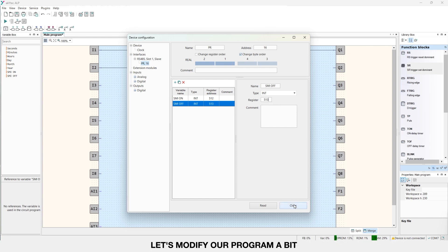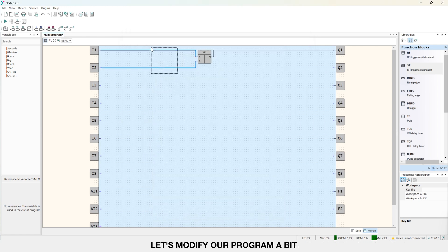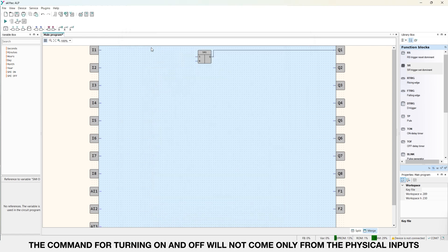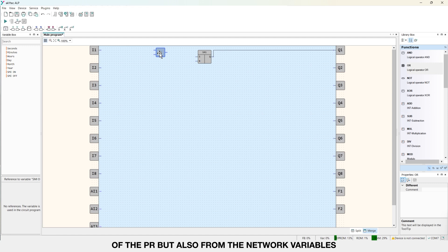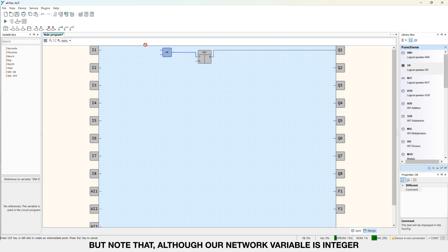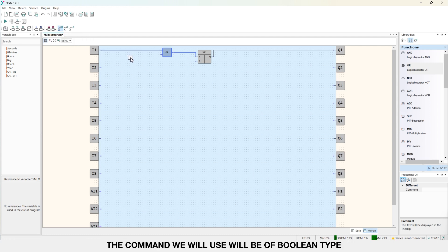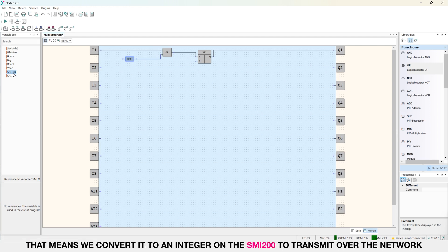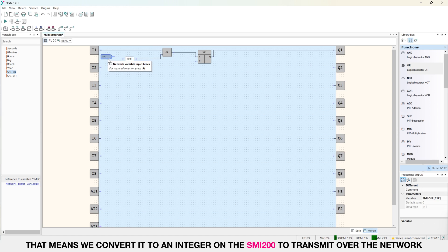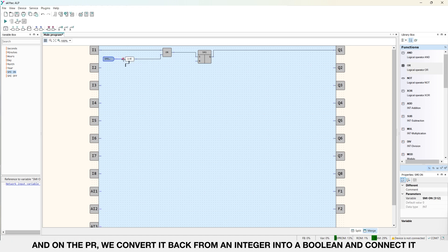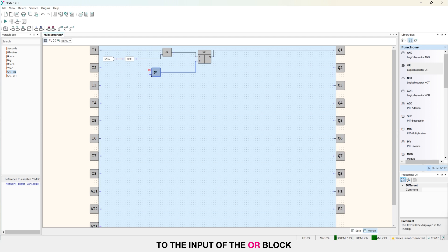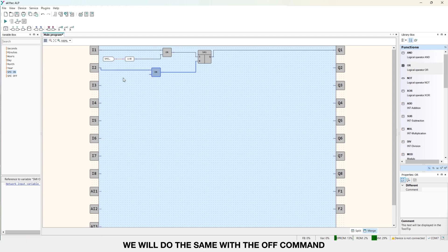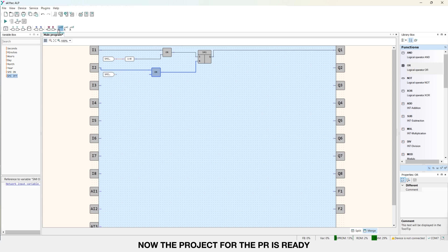Let's modify our program a bit. The command for turning on and off will not come only from the physical inputs of the PR but also from the network variables. But note that although our network variable is integer, the command we will use will be of boolean type. That means we convert it to an integer on the SMI200 to transmit over the network. And on the PR we convert it back from an integer into a boolean and connect it to the input of the OR block. We will do the same with the OFF command. Now the project for the PR is ready. Let's upload it to the device and move on to setting up the SMI200.